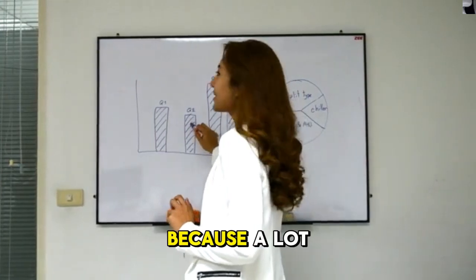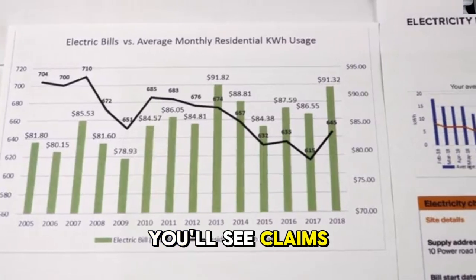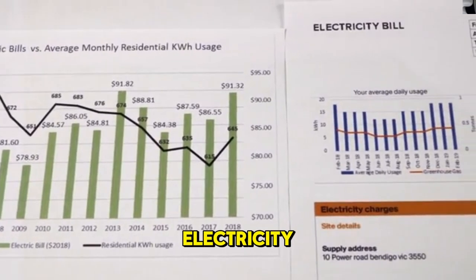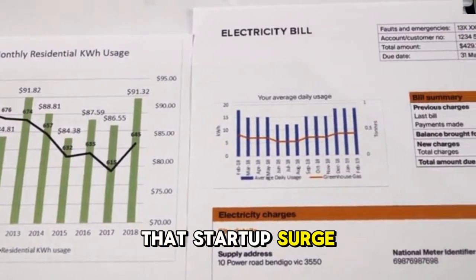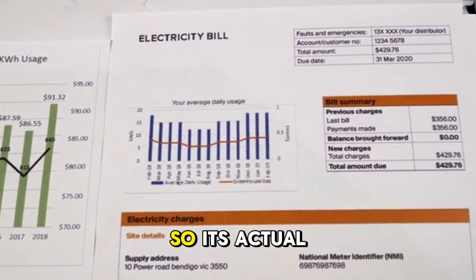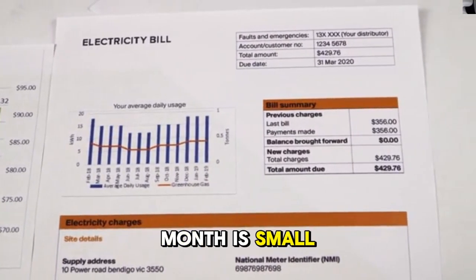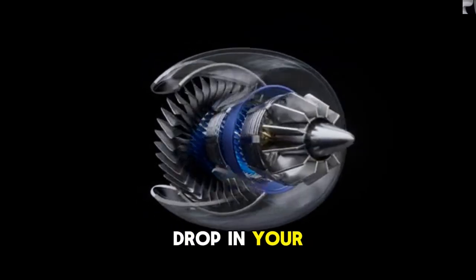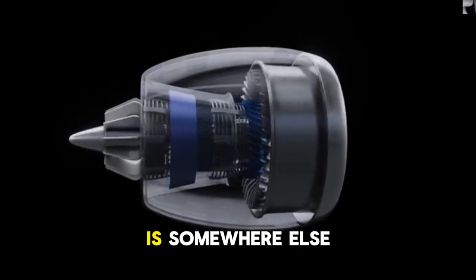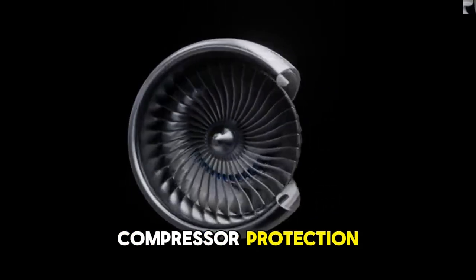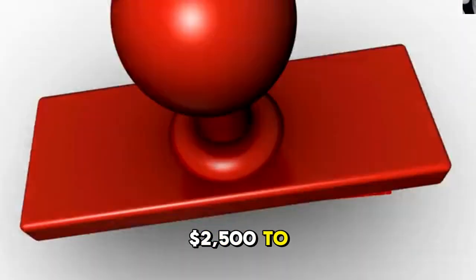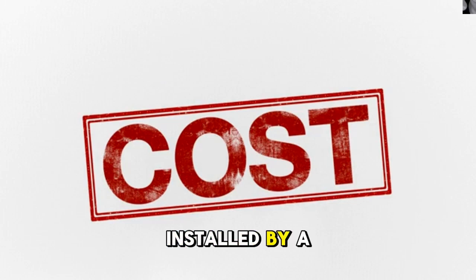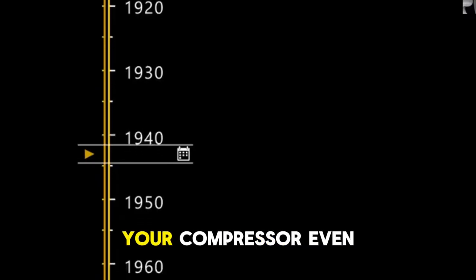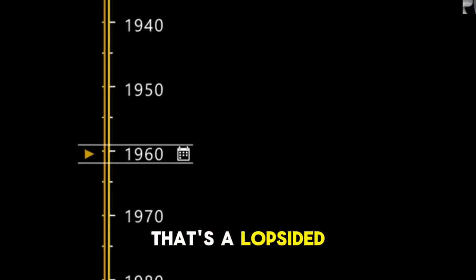Now, about the money. And I want to be straight with you here, because a lot of videos on this topic oversell it. You'll see claims floating around that a hard start kit will visibly shrink your electricity bill every month. In reality, that startup surge lasts a second or two out of an entire cooling cycle, so its actual effect on your total power usage over a month is small. If a video promises you're going to see a dramatic drop in your utility bill, be skeptical. The real payoff is somewhere else, and it's arguably bigger: compressor protection. A compressor replacement runs $2,500 to $6,500. A hard start kit installed by a licensed technician typically lands somewhere between $70 and $200 total. If it buys your compressor even 2 or 3 extra years of life, that's a lopsided trade in your favor. You're just not going to see it as a monthly number on your power bill.